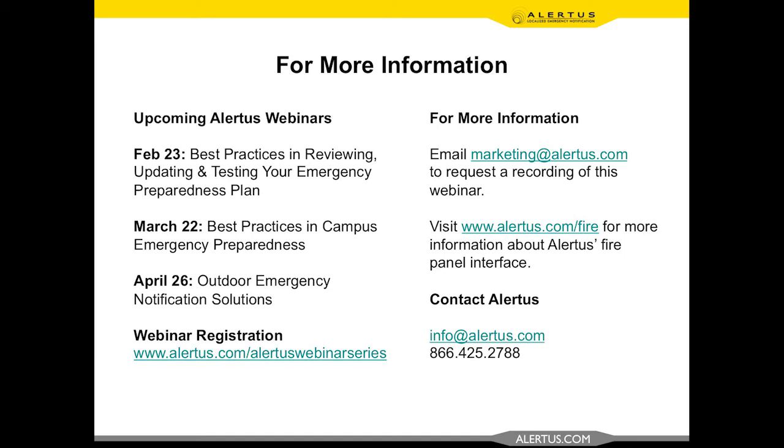Sure. So there are different types of events that we can have. Event triggers could be originating from the fire panel, as you were able to see. They could be coming off of a dry relay, so a panic button that we have, or any type of dry relay that is set off from another system. Also through an API. So if you have another system that can program to our API, we can set it up.